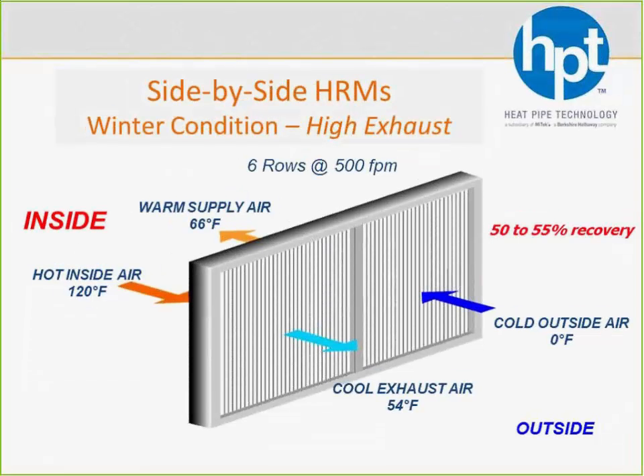So again, I mentioned that we can handle higher exhaust air temperatures. I wanted to run a quick example. We can actually go up to 200 degrees. That's as high as our refrigerant allows us to go. Our standard refrigerant, by the way, is R410A. We will go to 134A when we do our split passive, but we'll also go to it when that exhaust air temp is above 150 degrees, just because the peak of the P-H curve is higher for 134A than it is for 410, so we can handle a higher temperature.